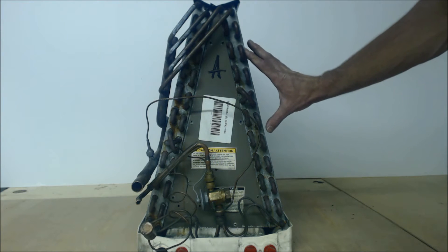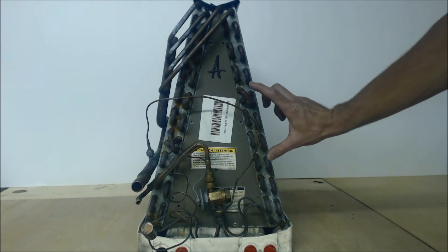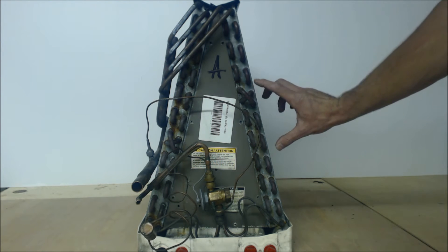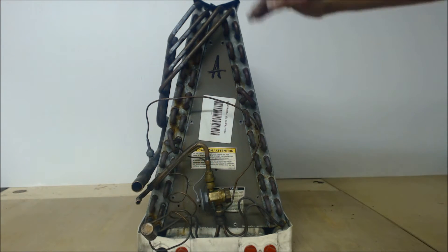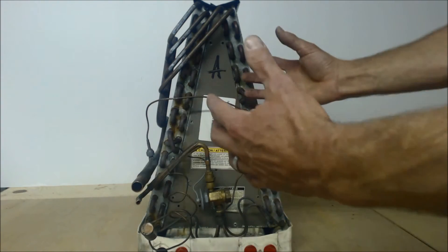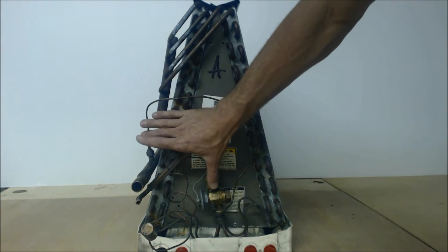You have 50% liquid, 50% vapor, say in the middle of the evaporator coil. After that, it turns into a complete vapor, and the temperature increase in the vapor form as it's absorbing heat from the house—that's called the superheat. So this TXV is measuring this actual superheat.